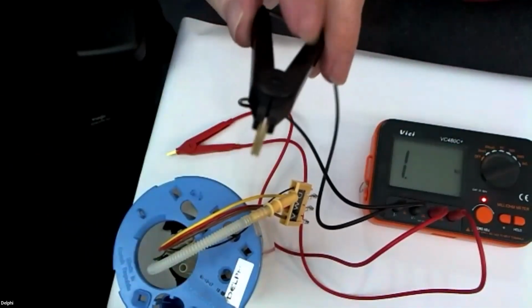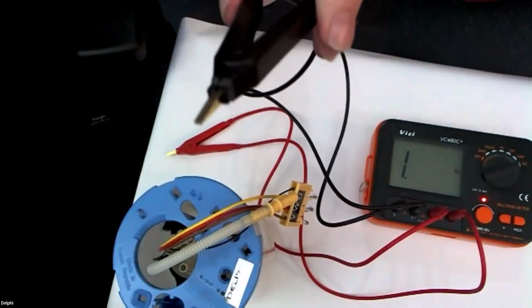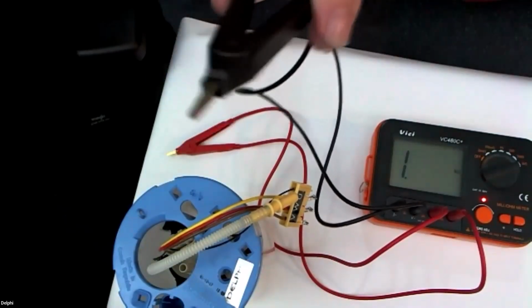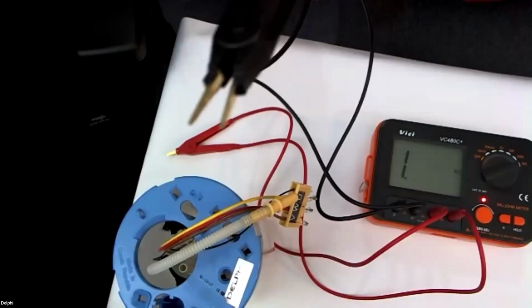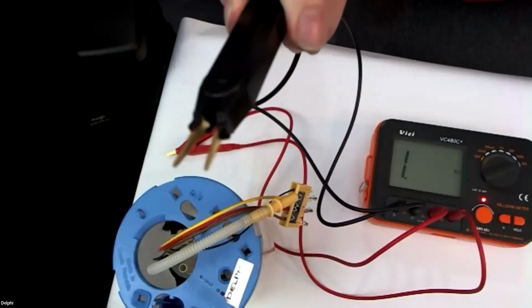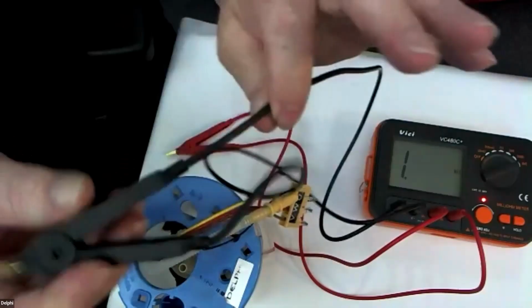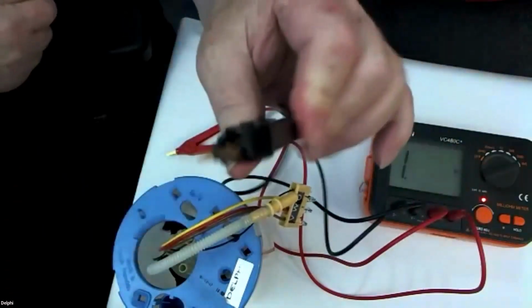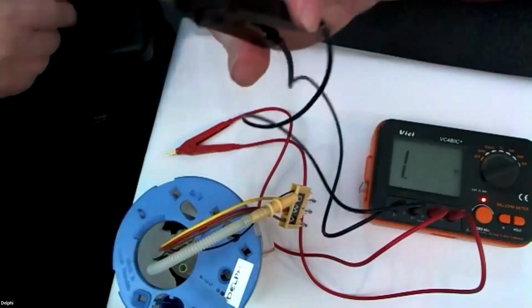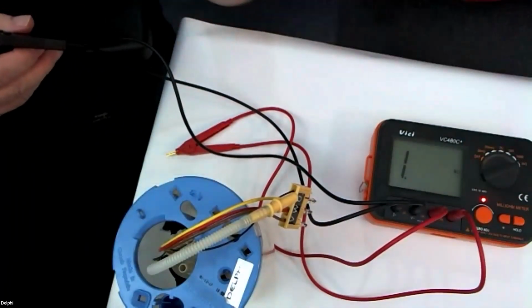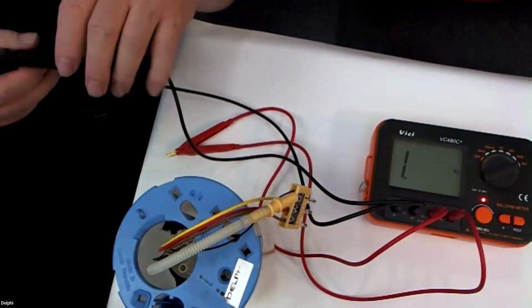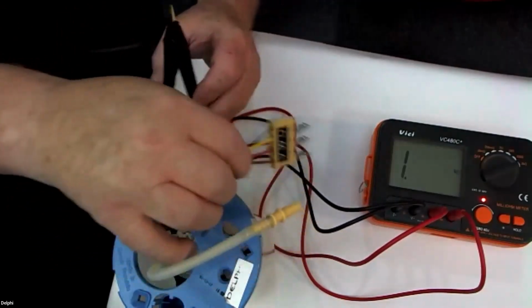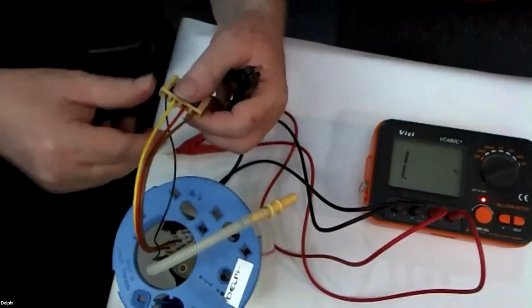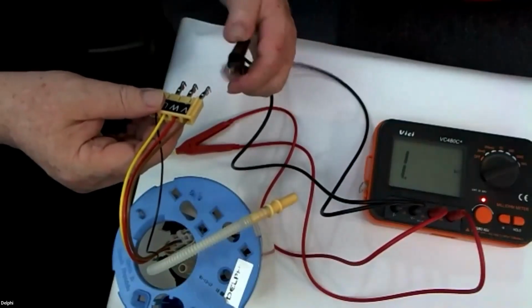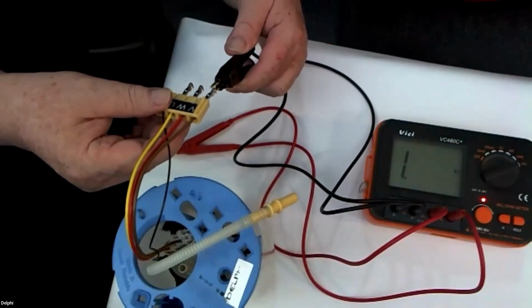They're called Kelvin clips, named after a guy like Kirchhoff or Ohm. Kelvin was one of those early Renaissance electronics inventors. The Kelvin clip is the reason you see 2 leads per alligator clip, so both jaws must touch. It's kind of like a push-pull design. That's how they can get a milliohmmeter to actually be a milliohmmeter. Otherwise it's just a fairly inaccurate ohmmeter good for higher resistances. This is stuff that's very low resistance, but it needs to be really precise.